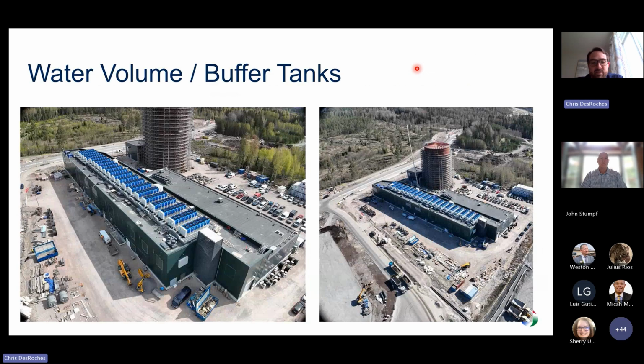Let me finish on a fun note. This is a project Swegon did in Finland. This is a 9 megawatt system, something like 4,000 tons of heating capacity. It's a large data center. They're recovering heat and boosting the temperature up for a district heating system and selling that to homes. But anytime we complain here about buffer tanks, just be thankful that we're not designing these big systems with heat pumps, because this big tank at the back is the buffer tank for the system. I thought at first this was an oil reserve tank for the generators, and they said, no, this is the buffer tank. I think it's 65 million liters of water.